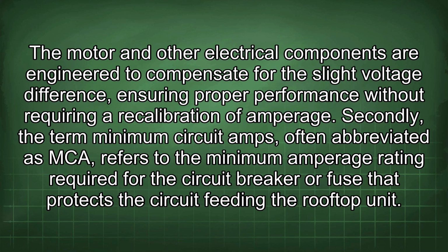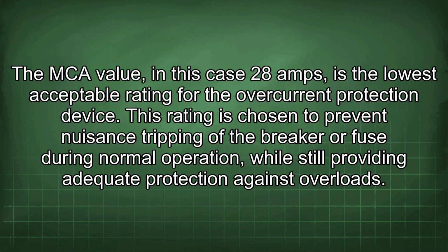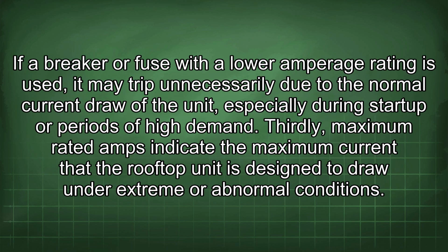Secondly, the term minimum circuit amps, often abbreviated as MCA, refers to the minimum amperage rating required for the circuit breaker or fuse that protects the circuit feeding the rooftop unit. The MCA value, in this case 28 amps, is the lowest acceptable rating for the overcurrent protection device. This rating is chosen to prevent nuisance tripping of the breaker or fuse during normal operation, while still providing adequate protection against overloads. If a breaker or fuse with a lower amperage rating is used, it may trip unnecessarily due to the normal current draw of a unit, especially during startup or periods of high demand.